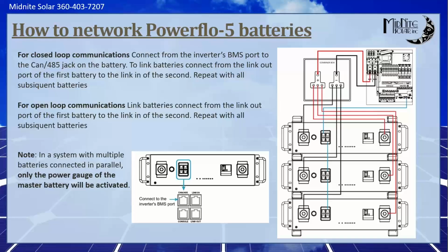You just got to balance what works best for you. If you're using a cabinet similar to the EG4 that has bus bars in it, and you put 6 batteries in, you can bring your inverter terminals out of the middle of that bus bar. Then you're really only crossing 3 batteries each direction. That works really well. It's about figuring out what fits your needs and what will carry the ampacity best, while keeping in mind that if the customer does something weird, like shuts off 3 batteries in a stack of 3, now is a small cable carrying too much current? There's a few caveats to think about.